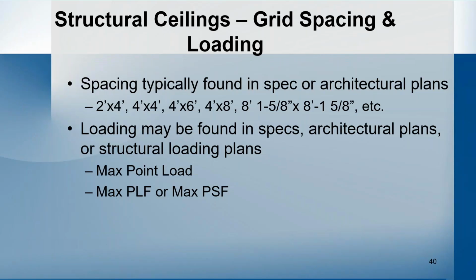And so for the grid spacings themselves, there's definitely a number of different spacings. Some typical ones, and you'll either find this in the spec or the architectural plans, are 2x4, 4x4, all the way up to an 8x8. And typically when you're looking at the 8x8, it comes out to 8 foot 1 5/8 by 8 foot 1 5/8. And so that allows for the panels themselves that fit within the ceiling system to actually be 8 by 8. And the extra 1 5/8 is to account for the strut members themselves.